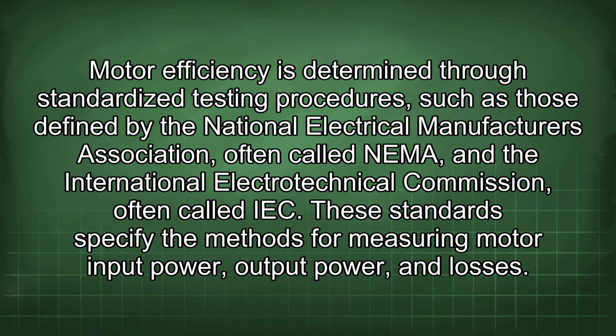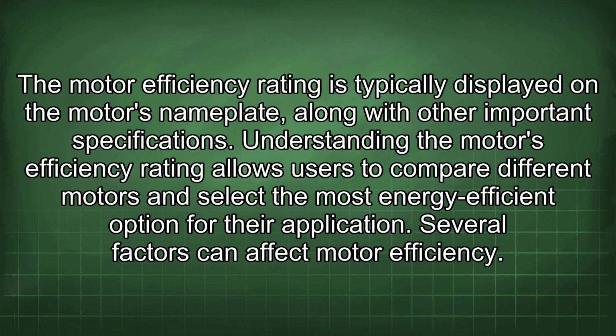Motor efficiency is determined through standardized testing procedures such as those defined by the National Electrical Manufacturers Association, often called NEMA, and the International Electrotechnical Commission, often called IEC. These standards specify the methods for measuring motor input power, output power, and losses. The motor efficiency rating is typically displayed on the motor's nameplate, along with other important specifications. Understanding the motor's efficiency rating allows users to compare different motors and select the most energy-efficient option for their application.